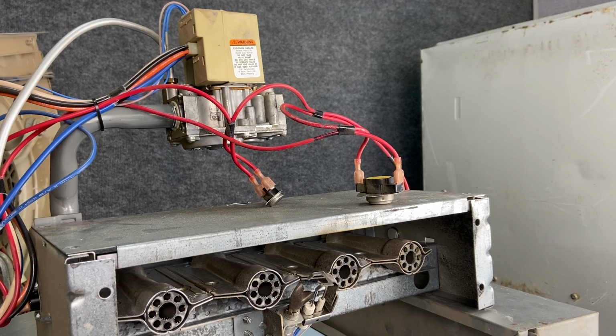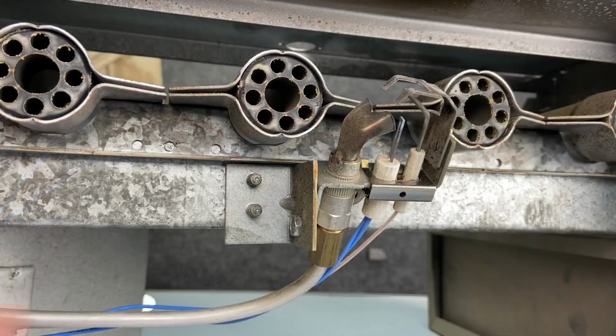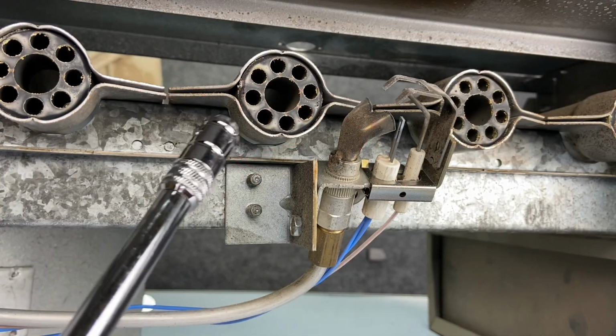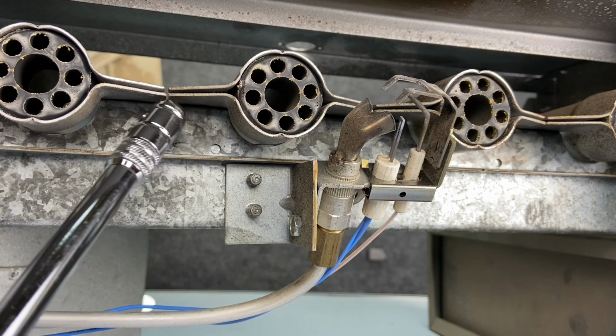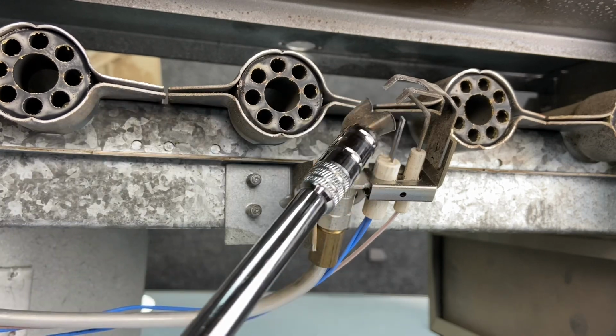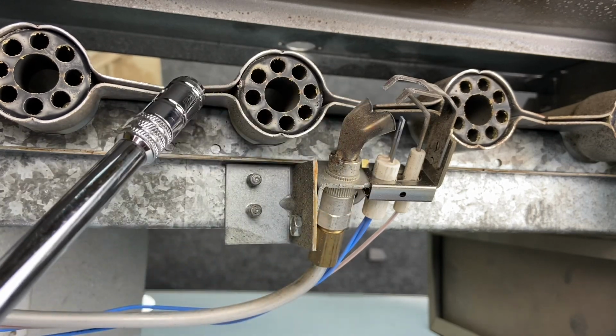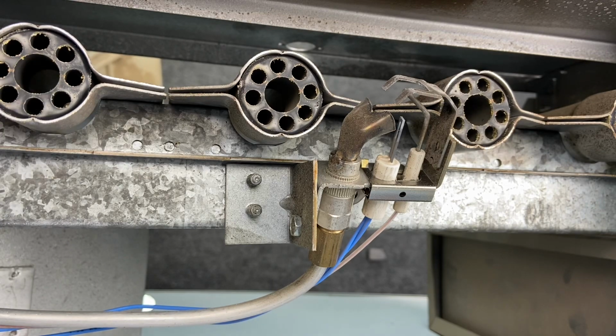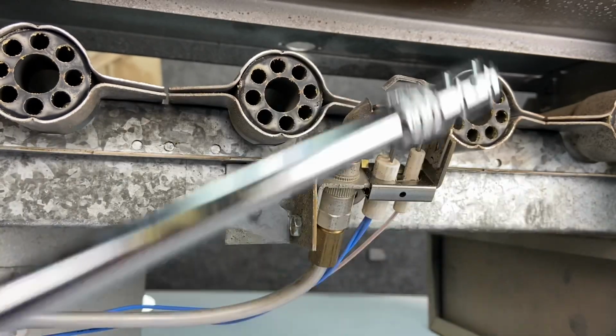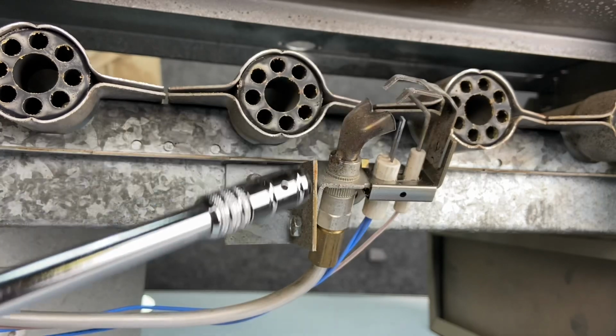Now what we want to focus on next is this part right here. This is going to be our intermittent pilot. This is going to be the thing that really makes this furnace come together. So I'm going to readjust the camera so we can get a better look. So in our burners, we were talking about earlier these crossover tubes. You can see this little split right here. Once we ignite our burners, it allows the flame to go across through to the next burner, ignite it, and so on. So these are little crossovers, but this section right here is our intermittent pilot assembly.